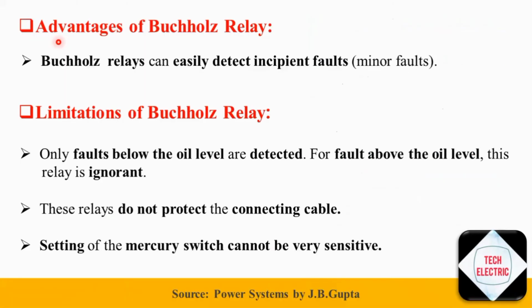Now the last topic of the session is advantages and limitations of Buchholz relay. The main advantage of Buchholz relay is that it can easily detect incipient faults, which are also known as minor faults. Minor faults include core heating and turns fault. As minor faults are easily detected, the transformer unit can be taken out of service before a major fault occurs.